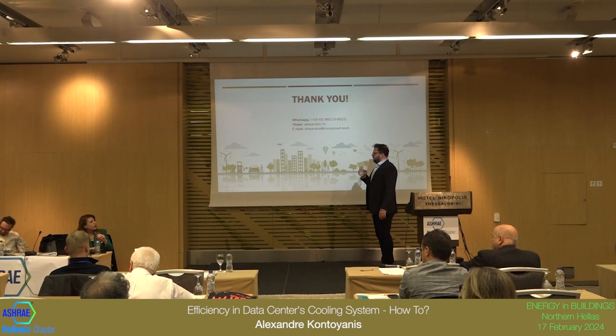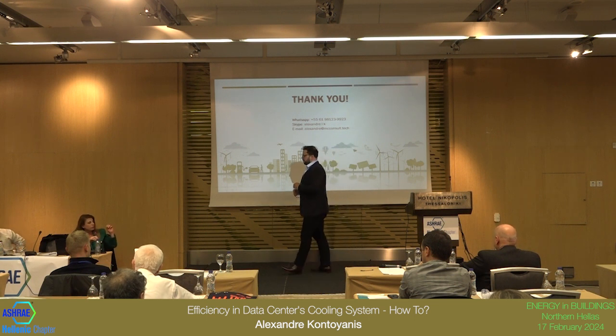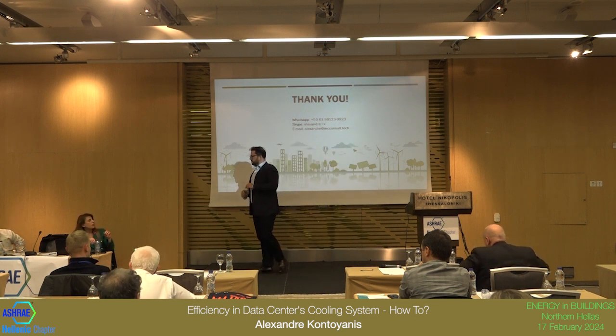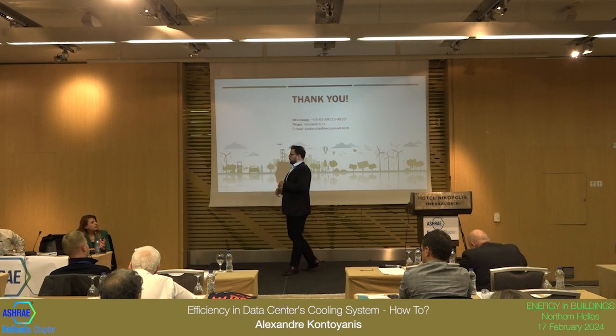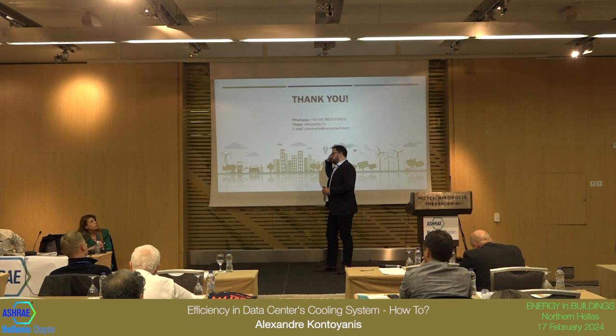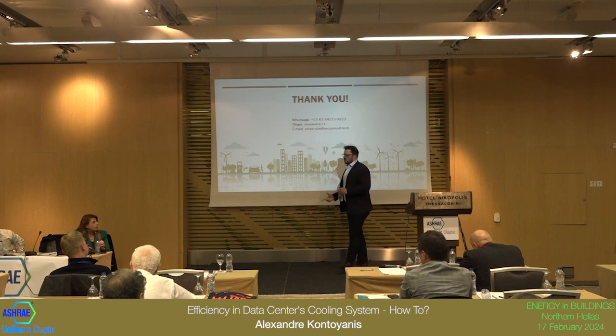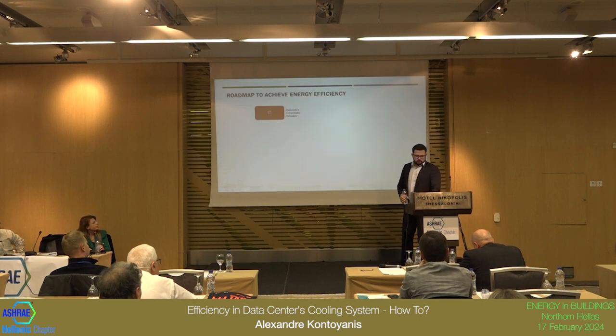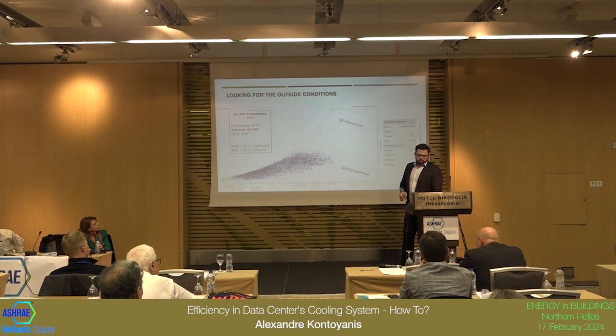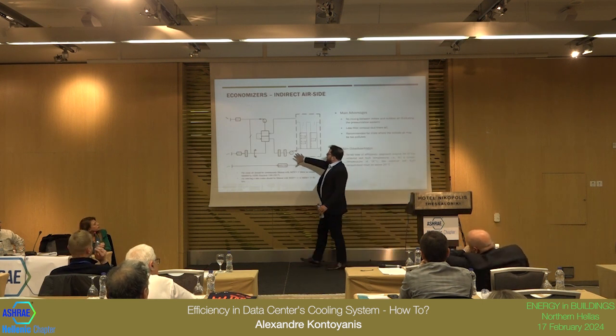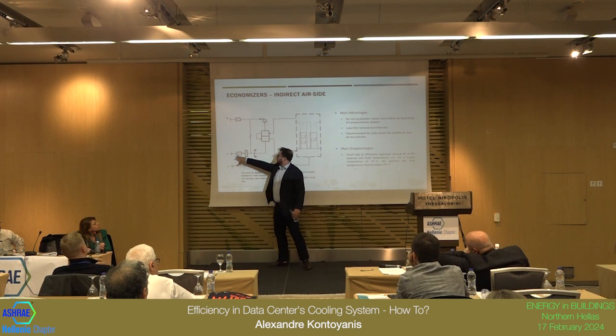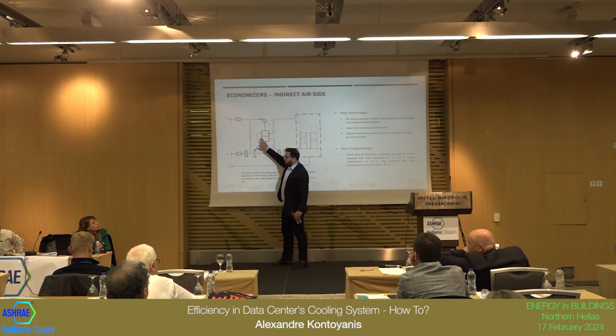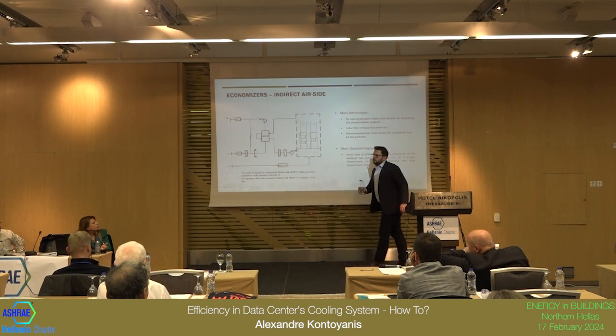Sure. Can you explain again, as quickly as possible, how it is manageable not to use chillers in Thessaloniki for a temperature of 27? With what exactly method? How not to use chillers? With dry bulb, you mean, or wet bulb 27? If you see here, many vendors have this type of equipment, and you can use it here in Thessaloniki. This type of equipment lets the outside air just flow through, even at 38 degrees outside in Thessaloniki, but that is dry bulb temperature.